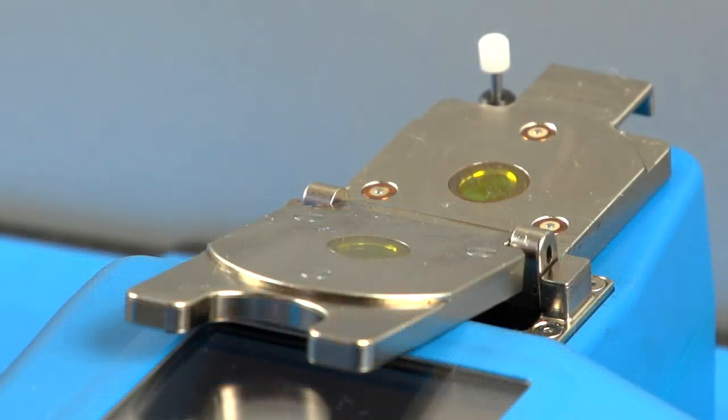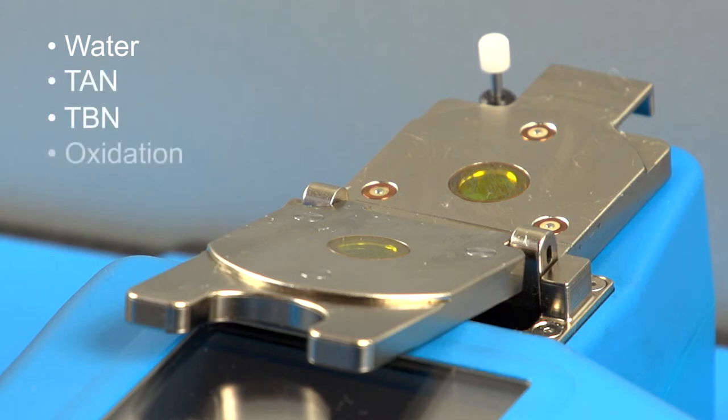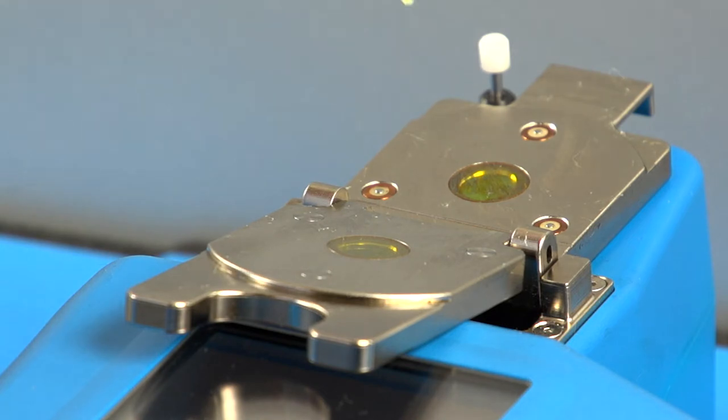The FluidScan infrared spectrometer measures water content and oil chemistry. Parameters such as total acid number, total base number, oxidation, nitration, and sulfation as well as other oil specific properties are measured. A single drop of oil is placed in the flip-top cell.